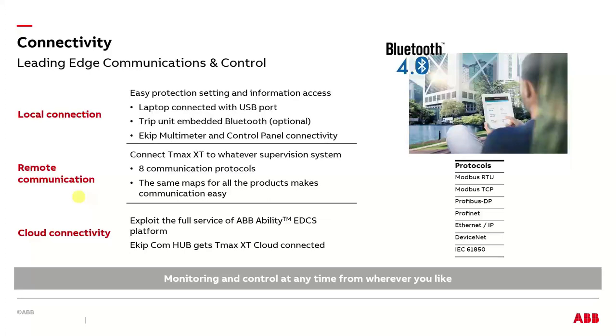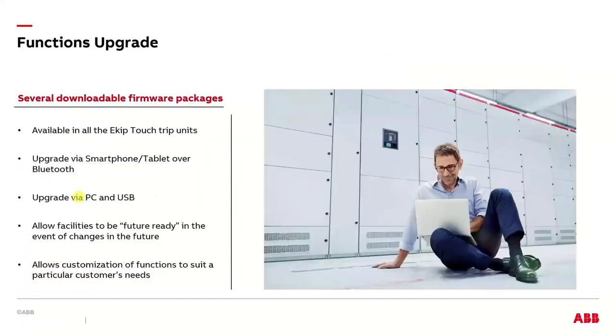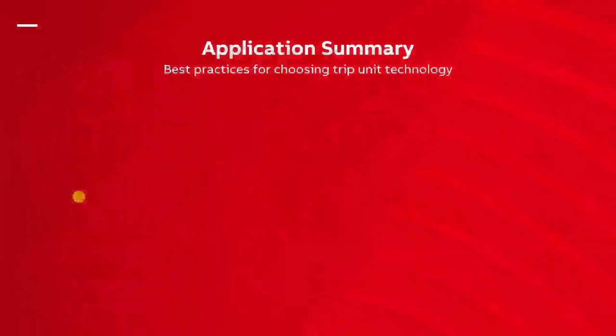So that's kind of a nice arc flash safety feature. And then this T-Max line of breakers, you can actually download new functions to them. So you could buy a simple package of functions, and then if you find out down the road you need some frequency protection, well, you can then download that package and install it to the breaker, so it doesn't require replacing the breaker or taking it out of service. You can do it on the fly remotely over a network. So we're calling it a kind of future ready feature.